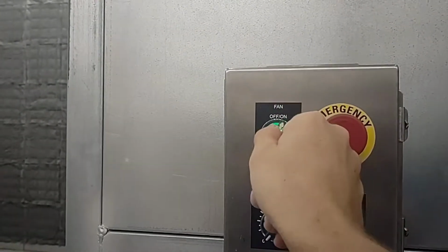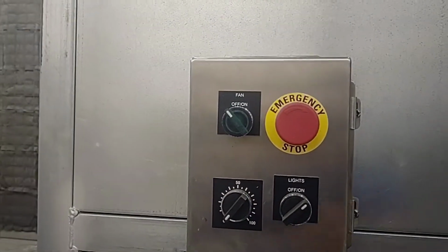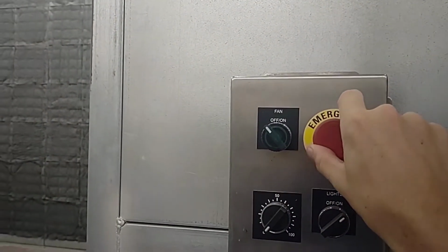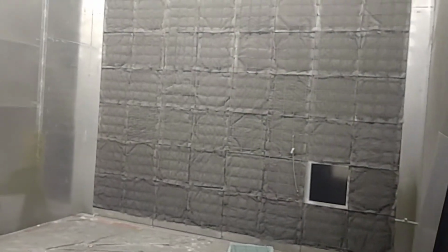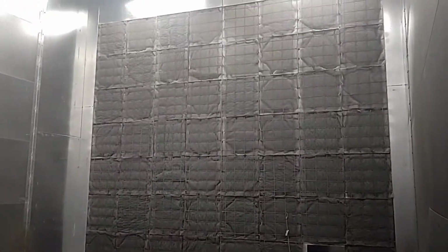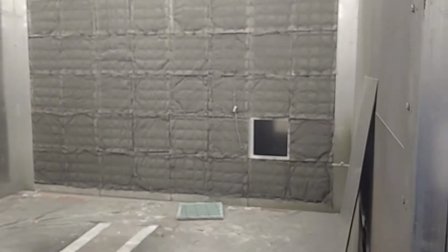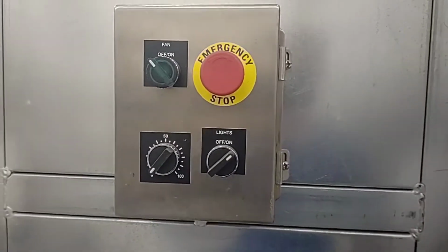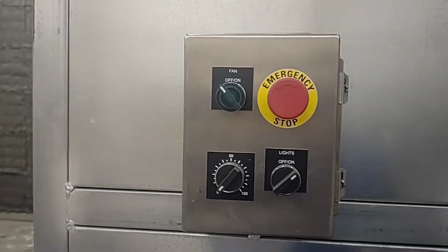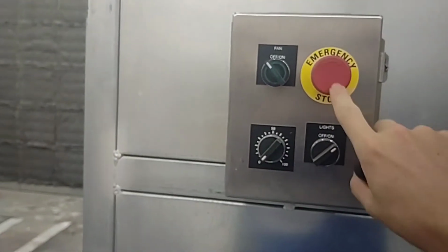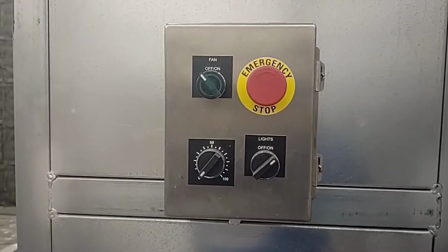Fan on and off switch, simple enough. And then we have an emergency stop switch here, just in case, hopefully never, for some reason one of these filters decides to go rogue and get sucked up into that giant fan, we want to be able to stop it as quick as possible and not let it do the normal 10-second ramp down that it's programmed to do.